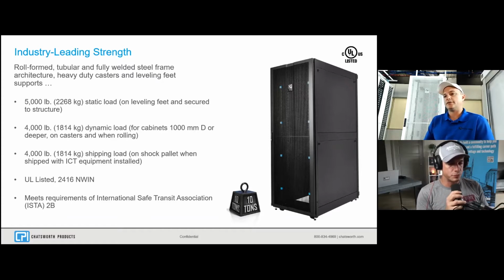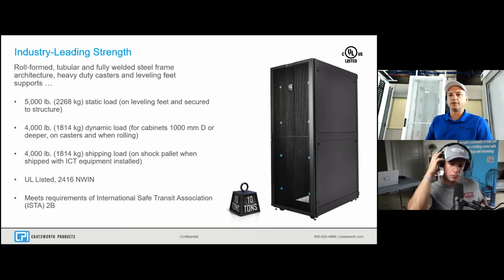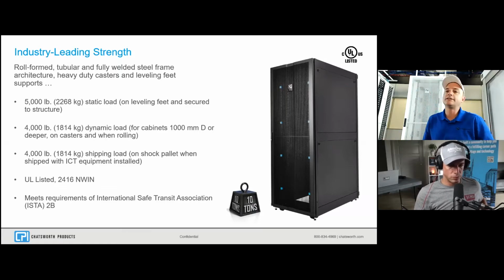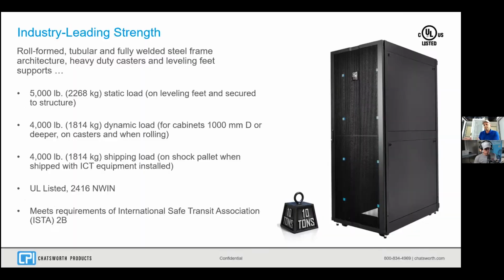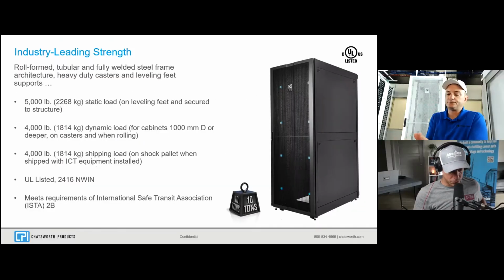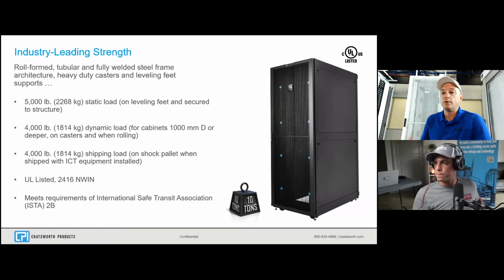Also, ZetaFrame is UL listed under 2416. There are a number of different requirements to achieve that listing, and with respect to load rating, one of those tests is a 4 times test—whatever load rating a manufacturer advertises, you have to test the product to 4 times that amount. With ZetaFrame having a 5,000 pound load rating, we actually applied 20,000 pounds of force to this frame, and it passed. It's an extremely strong frame.